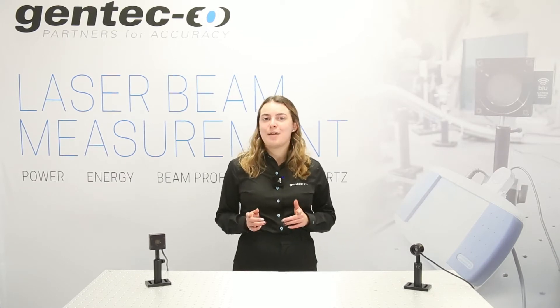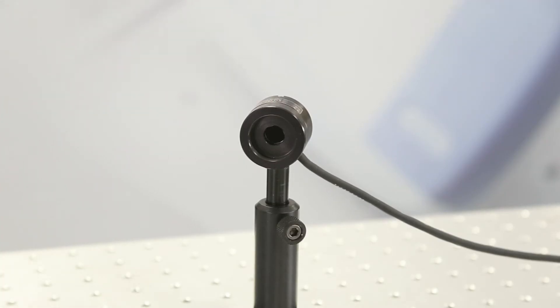A photodetector is made from semiconductors. These detectors use what we call the photoelectric effect, meaning that they convert photons from a light source into an electric current that can be calibrated to measure power. The Gentec-EO PH100 detector that you can see here uses this technology.